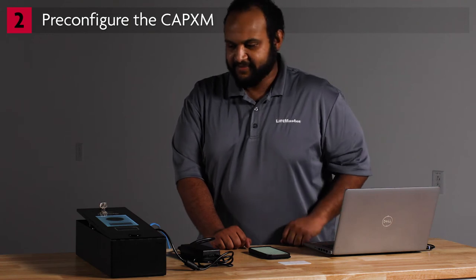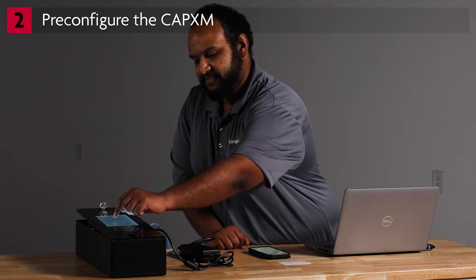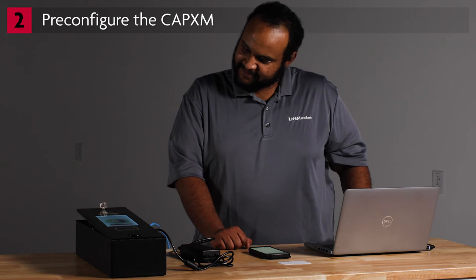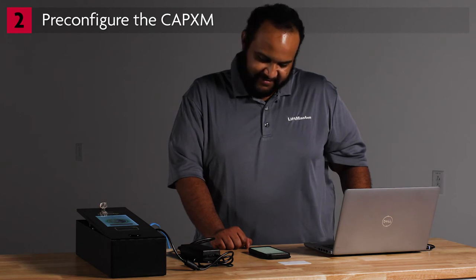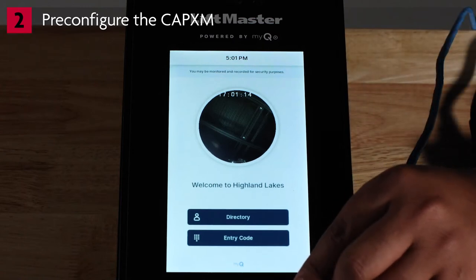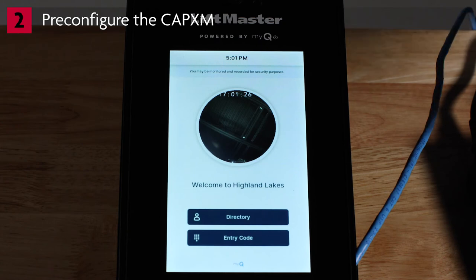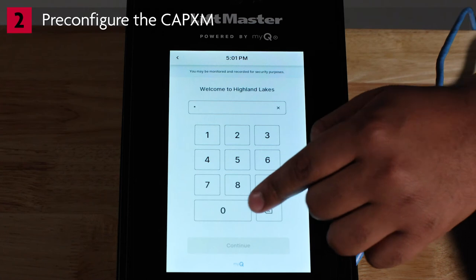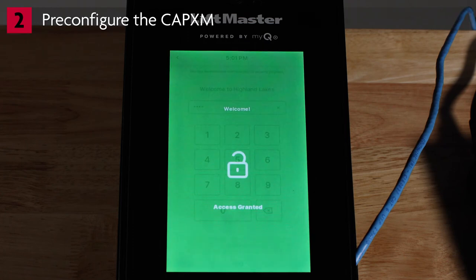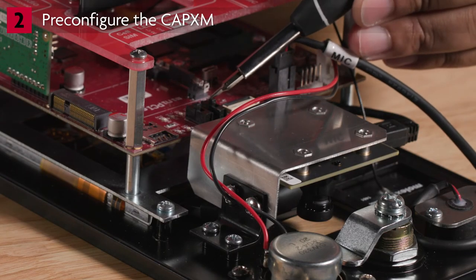Next, test granting access via a regular phone call. Tap the Directory and search for your own name, then call yourself. The app will receive the incoming call. Do not answer the call using the app — after 30 seconds, the call will roll over to your regular phone. Answer the call and press 9 to grant access. Also test credentials: touch a card to the card reader. The controller will click, but the LCD screen will not show any message. Test the entry code: tap Entry Code, enter the code on the numeric keypad, and tap the green Enter button. The LCD screen will display Access Granted. To ensure the CAPXM boots in admin mode the next time you power it on at the job site, flip DIP switch number 1 to the ON position. Disconnect power to the controller and prepare it for transportation to the installation site.